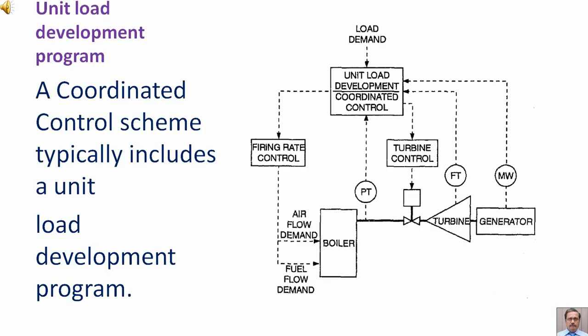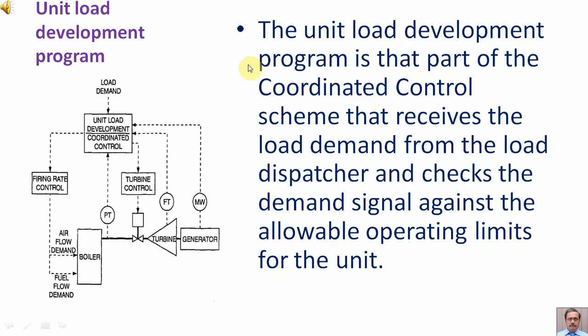A coordinated control scheme typically includes a unit load development program. The unit load development program is that part of the coordinated control scheme that receives the load demand from the load dispatcher and checks the demand signal against the allowable operating limits of the unit.